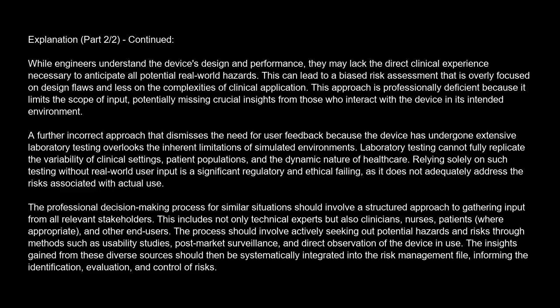A further incorrect approach that dismisses the need for user feedback because the device has undergone extensive laboratory testing overlooks the inherent limitations of simulated environments. Laboratory testing cannot fully replicate the variability of clinical settings, patient populations, and the dynamic nature of healthcare. Relying solely on such testing without real-world user input is a significant regulatory and ethical failing, as it does not adequately address the risks associated with actual use.